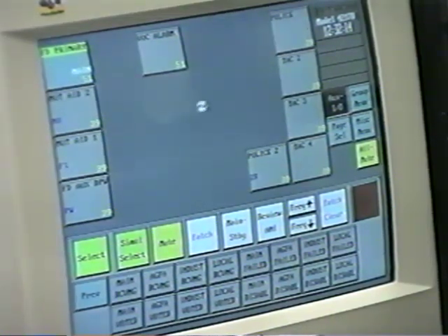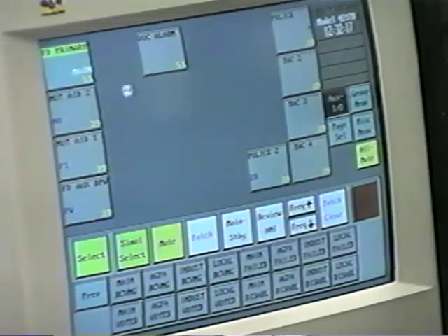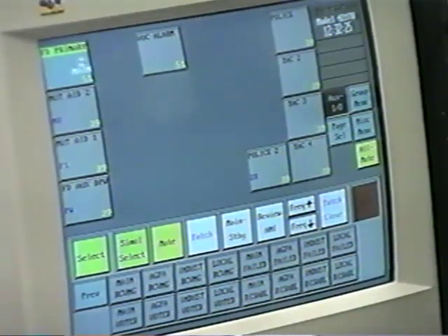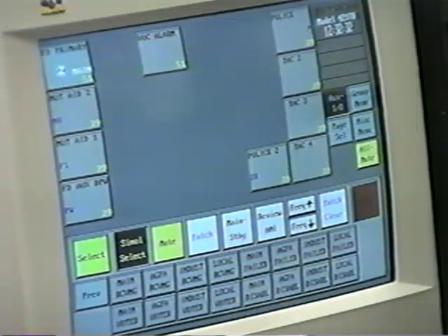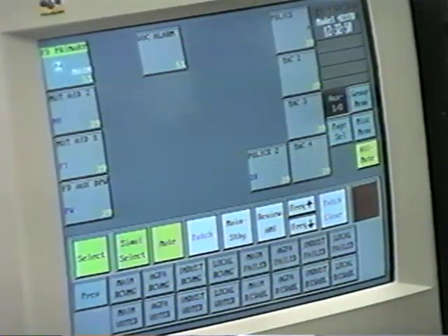And as you can see, this is fully mouse driven. Second function I talked about was simulcasting. If the fire dispatcher wants to give a message over the in-house VOC alarm as well as the fire radio system, they would select simul-select, select the fire module as well as the VOC alarm module. As you see, both have a green highlight bar. When the dispatcher transmits, it'll go over both. And you can reverse the process to disable the simulcast.